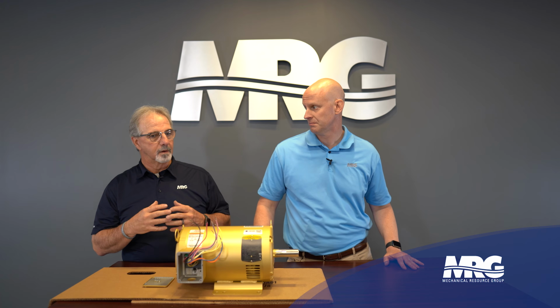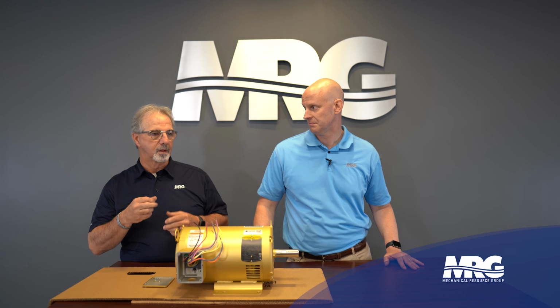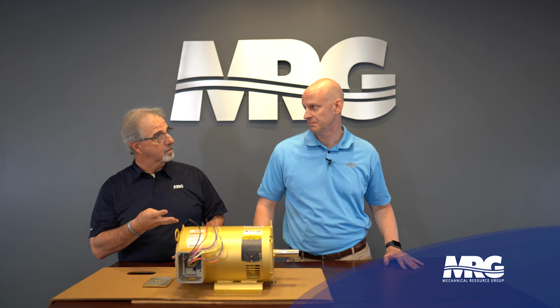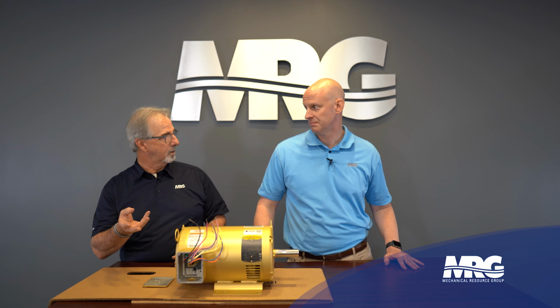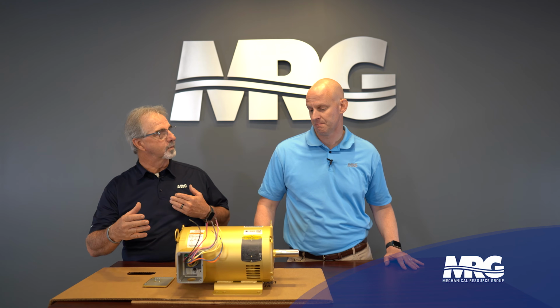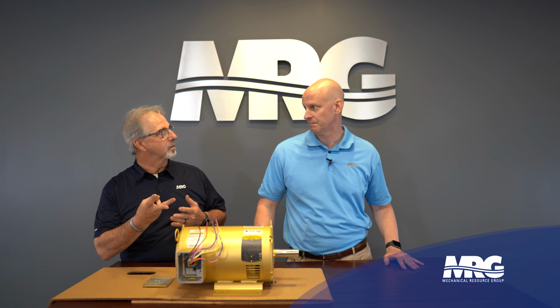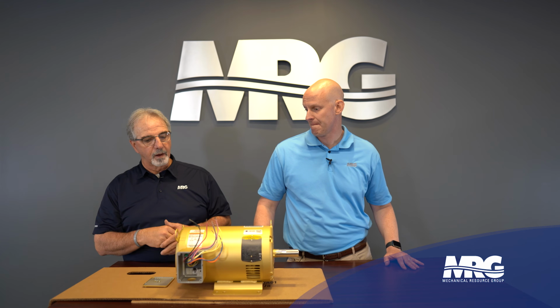The way that you'll get a motor delivered is you'll either have 3 leads, 6 leads, 9 leads, or 12 leads. If you'll notice, they're in multiples of 3-phase motors. So this particular motor that we're looking at right here.